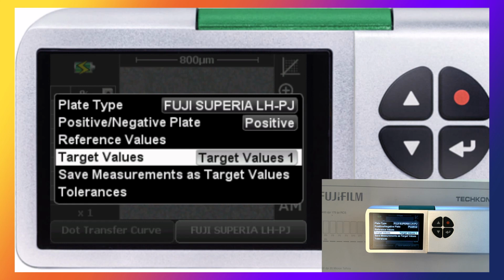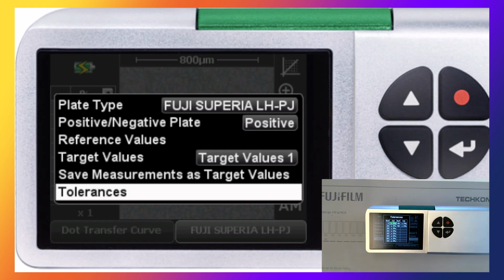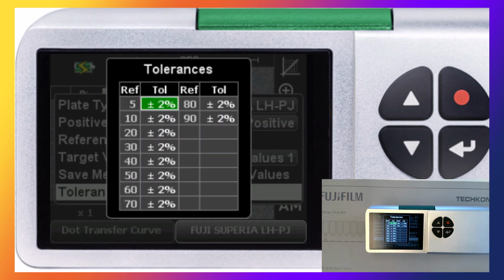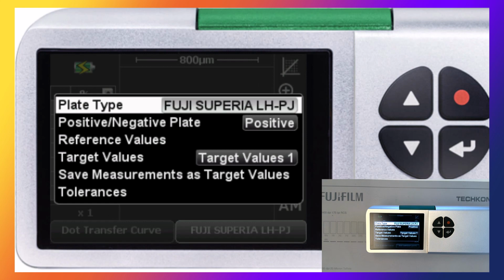One last thing you can change before using the dot curve function is the tolerance. The tolerance determines which color you will see after the measurement. If it's within the tolerance, the value will be highlighted in green. If it exceeds the tolerance, that value will be highlighted in red. Alright, now I'm ready to measure.